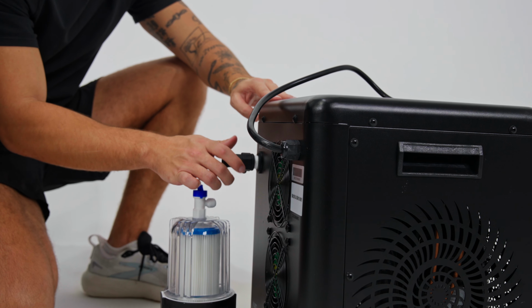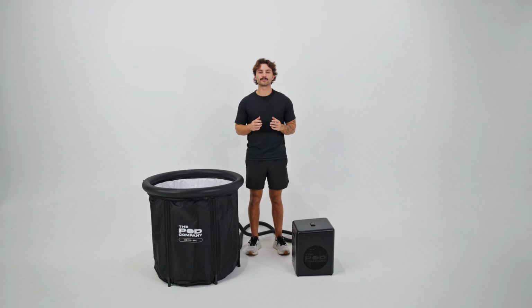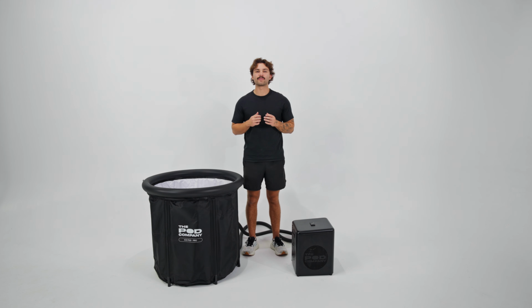Start by taking one hose and clicking it onto the filter canister. Then connect the other end to the lower drain valve on your pod. Next, take the second hose and connect it to the outlet port on the chiller. Then attach the other end to the upper drain valve. At this point, everything is connected and your setup is physically complete. And if you're wondering about the filter key, don't worry. You don't need it for setup. It's only used during cleaning, which we'll cover later. With everything connected, let's move on to getting your chiller powered on and started up properly.